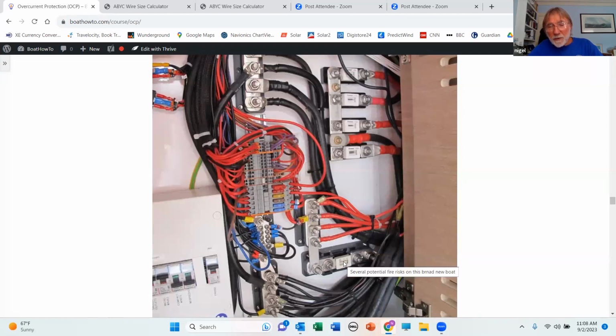The ampacity of this fuse, the amp rating, is guaranteed to be higher than the ampacity of this conductor. Because if it's not, every time one of these circuits is loaded up, you're going to blow the fuse. So this conductor is not protected. The likelihood is that none of these are either, because if the ampacity of this fuse is low enough to protect these conductors individually, and all these circuits are running at the same time, the fuse is going to blow. So we probably have none of these circuits adequately overcurrent protected.